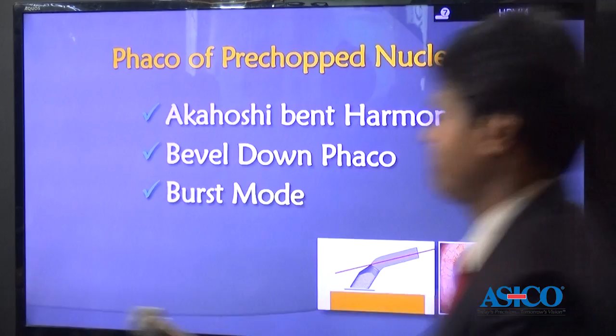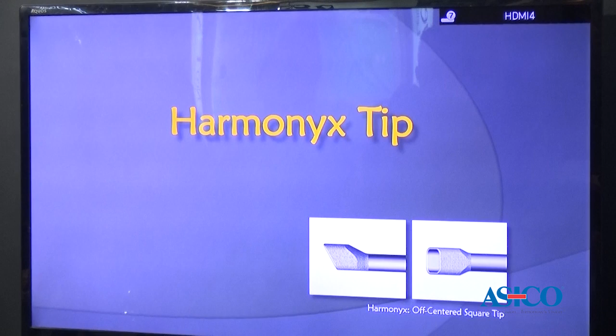Now I'd like to talk about the phacoemulsification of the pre-chopped nucleus. After phaco pre-chop, I use a bent Harmonyx phaco tip bevel down, and I will use the burst mode. I'd like to explain about the Harmonyx tip. It was formerly called the off-centered wobble tip, square wobble tip. This tip was originally developed for the torsional handpiece from Alcon.